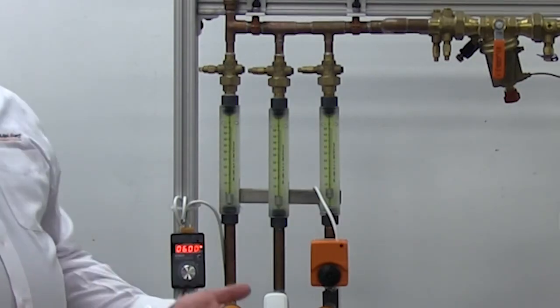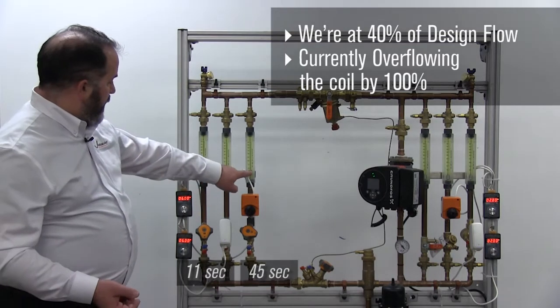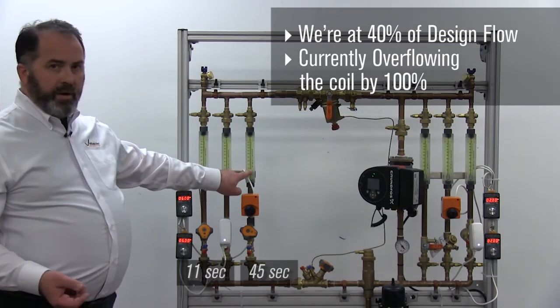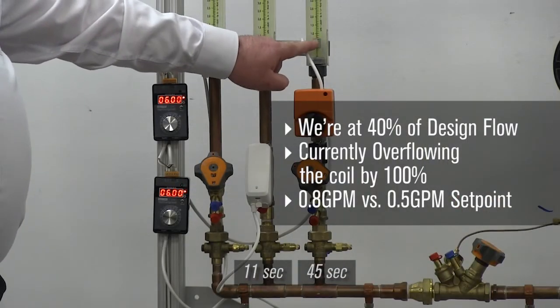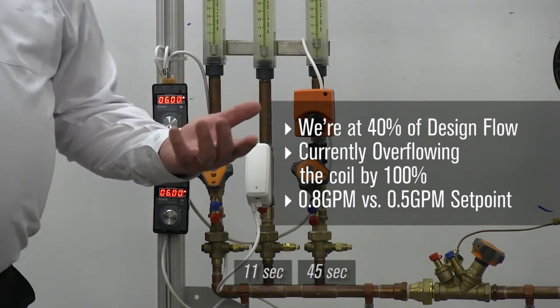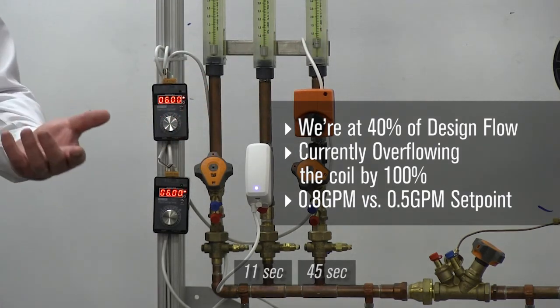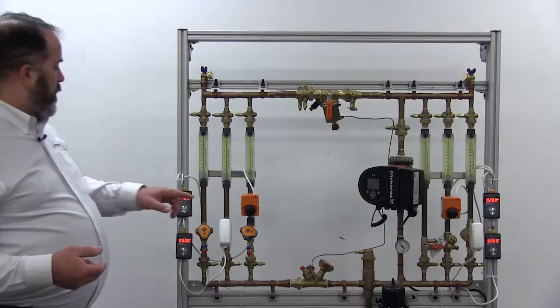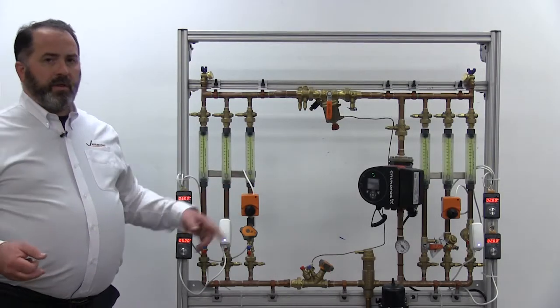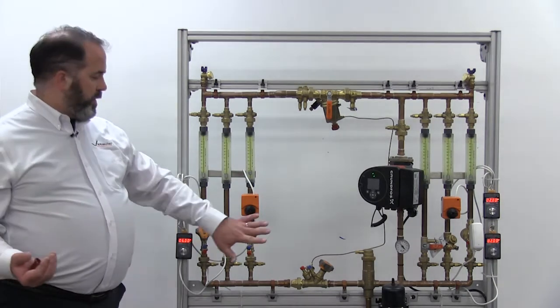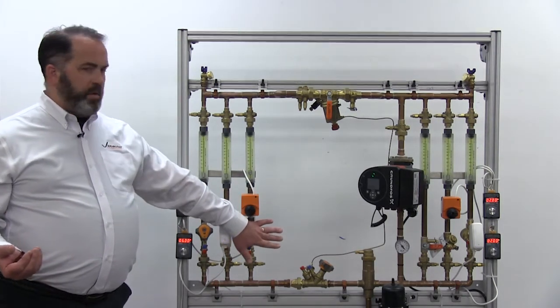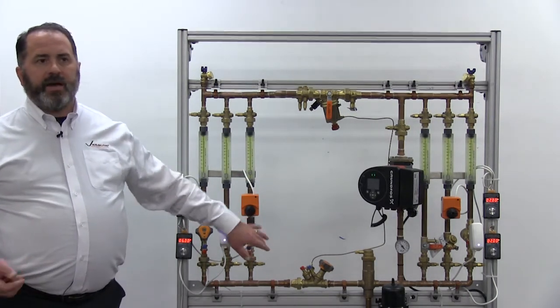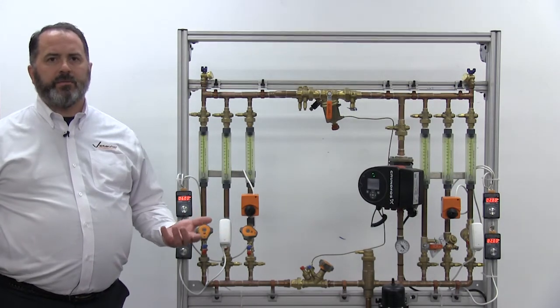Now our other control valve has finally gotten there, but you'll notice that we're nowhere near where we need to be. We're at roughly 40% of the flow rate, so we're twice the flow rate we need to be, so we're overflowing by 100%. Why is that? It's due to the lack of authority we've given to control valve. We're basically taking all of the authority away by adding a separate balancing valve in order to be able to get the flow to where we need it for design point.